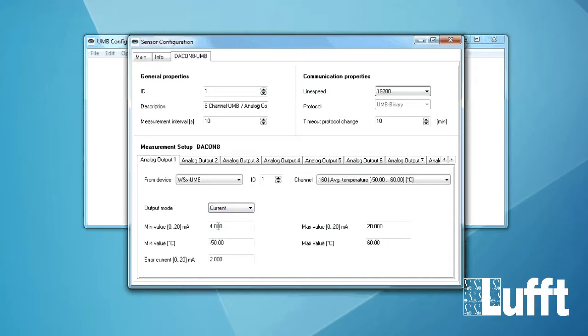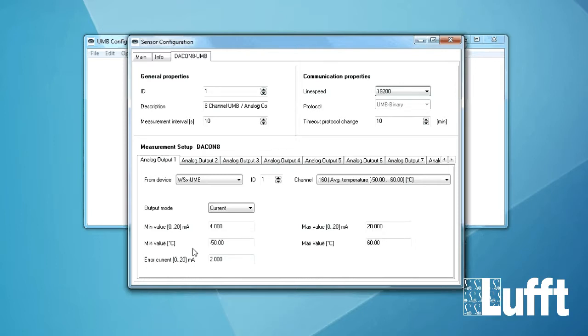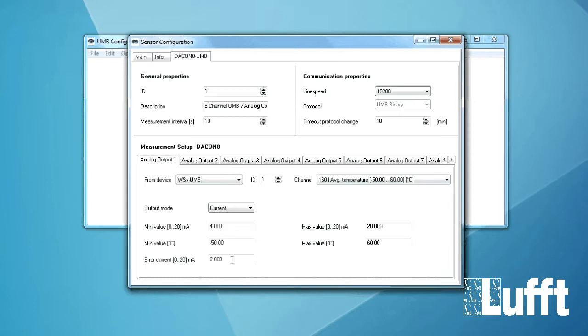Then you have the minimum value of the current which is 4 mA and you have the maximum value which is 20 mA. You can of course also set it to between 0 and 20 mA if you want. Then you have the minimum value of the temperature which is minus 50 and the maximum value which is 60. And our error current that means if some error occurs on this channel the analog output will be 2 mA.